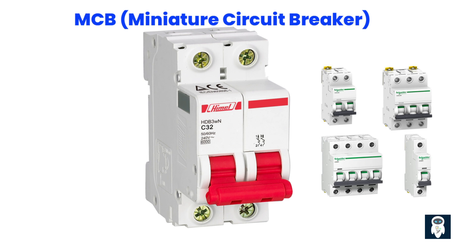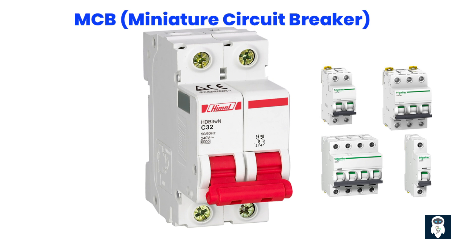MCBs are compact and designed to fit into standardized electrical distribution boards. They consist of a switch mechanism that opens the circuit when an overcurrent or short circuit is detected. The switch is connected to a bimetallic strip or an electromagnetic coil that senses the current passing through the circuit. If the current exceeds the predetermined threshold, the switch is tripped, breaking the electrical connection and disconnecting the faulty circuit.